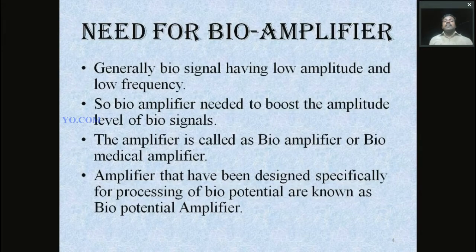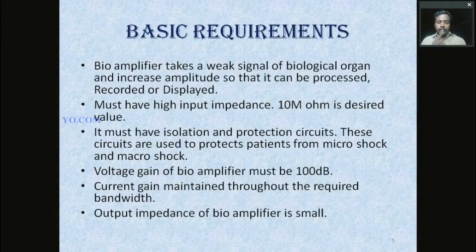So here the question is, what is the need of a bioamplifier? Generally the need is the first two points. The biosignals are very weak signals, with very low voltage and very low frequency. So in order to increase the amplitude, we use a biological amplifier. The biological amplifier amplifies the input signal and produces some level of volts. So that is the need for a biological amplifier.